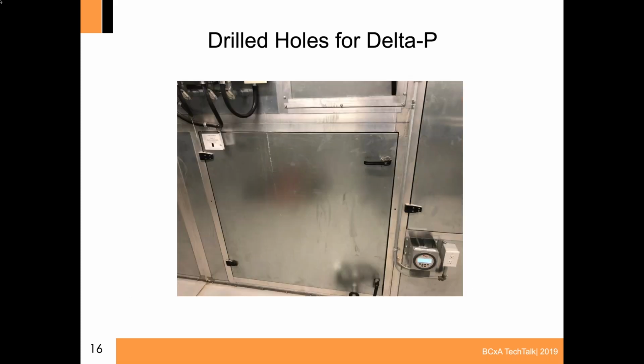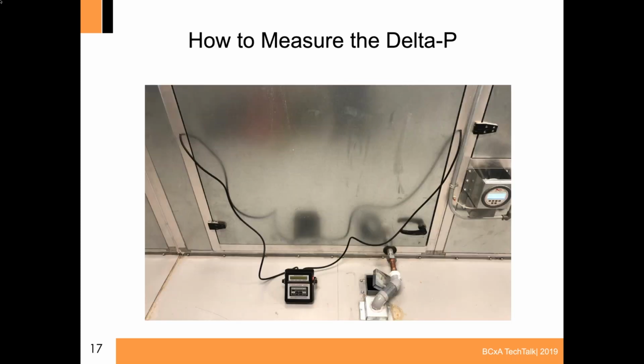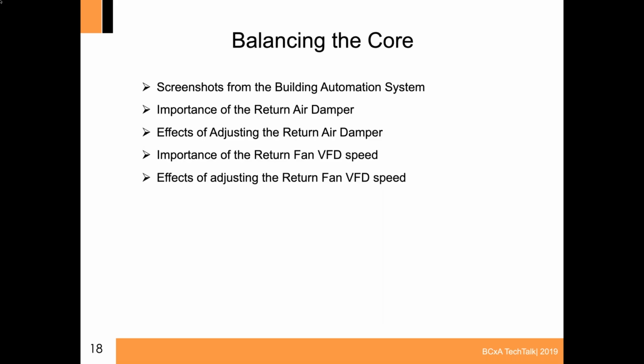So what we did is drilled holes on either side, and hopefully in the middle there you can actually see those two little holes that were drilled. And we installed our tubing across that with a measuring device that we got from a flow hood that we use for verifying balancing. So balancing the core. The next set of screenshots are going to be actually from the building automation system, as well as pictures of our measurements and a calculation showing how much flow we were getting before and after.